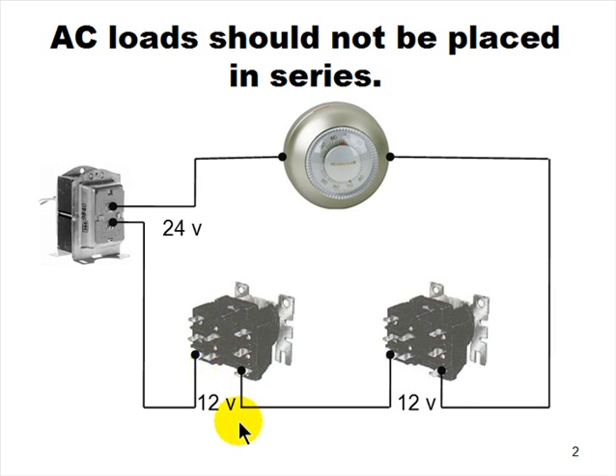A 24-volt coil ain't going to pull in on 12 volts, any more than a 120-volt motor is going to run on 60 volts. Ain't going to happen. We don't put things in series. Put 2 zone valves in series, neither of them are open.